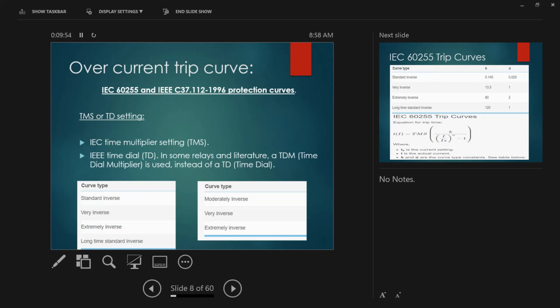The overcurrent trip curve comes from IEC 60255. We should have that in our test sheets, as I said before. There are two kinds of curves, and sometimes we get a mix-up. The IEC uses TMS, or time multiplier setting, which is sometimes mentioned in the relay settings. But if the relay says time dial, it means it's using the IEEE standard. TMS is IEC, so you see both sides.